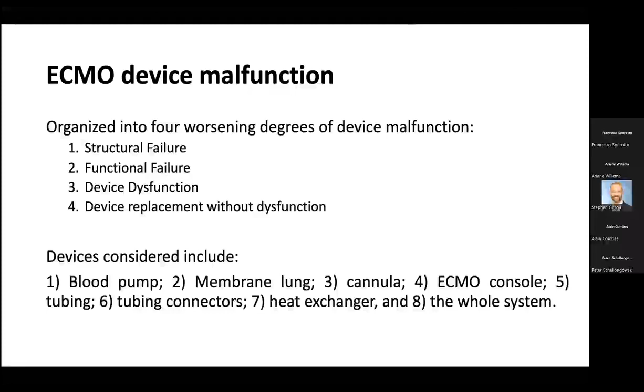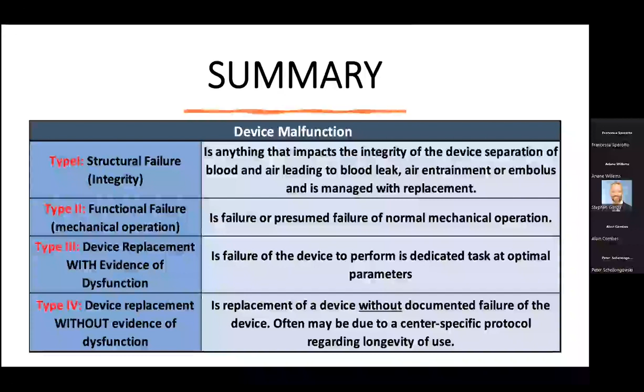Type 2 is a functional failure, basically a mechanical operation failure. It's a failure or presumed failure of normal mechanical operation of any component of the ECMO system. Type 3 is a device replacement with evidence of dysfunction, a failure of the device to perform its dedicated tasks at optimal parameters. And type 4, unique to ECMO, is a device replacement without evidence of dysfunction. Here the device is replaced without documented failure, more often due to a center-specific protocol regarding the longevity of use of the ECMO system.